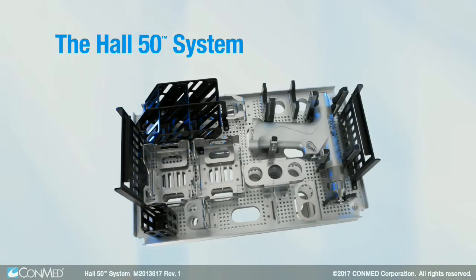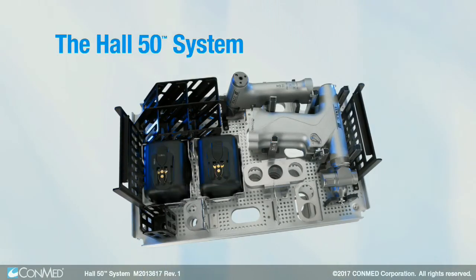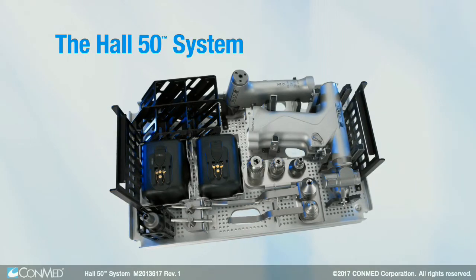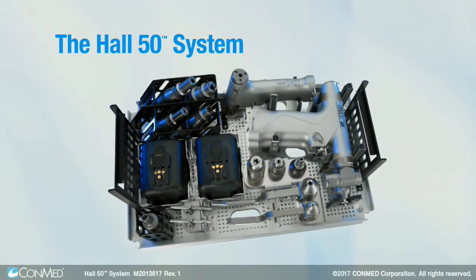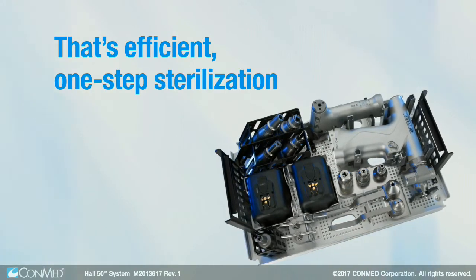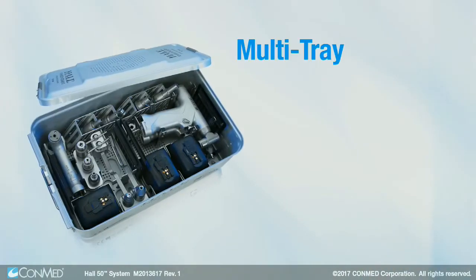The Hall 50 system is the only powered instrument system that allows the batteries, handpieces, and attachments to be sterilized together in the same tray at the same time. That's efficient one-step sterilization.